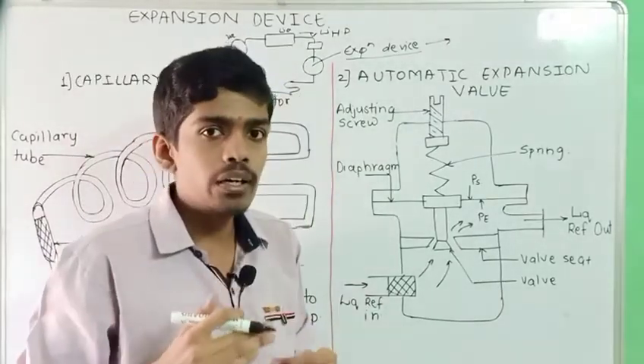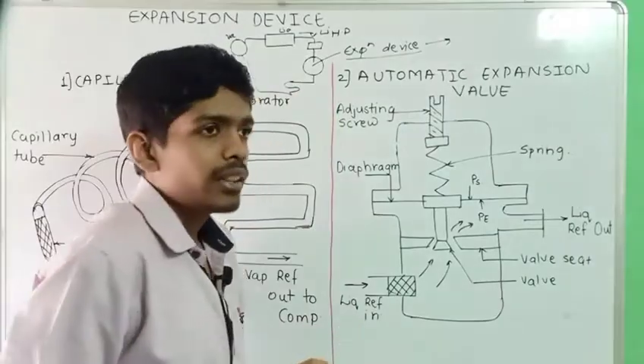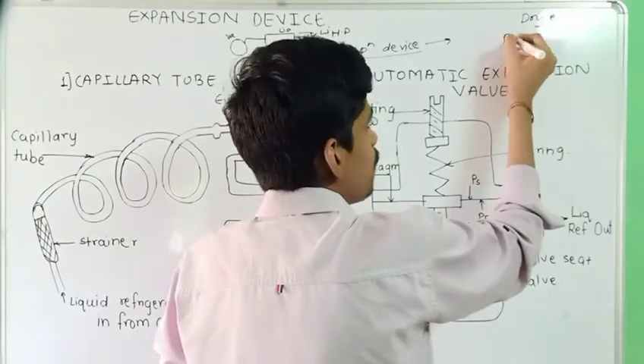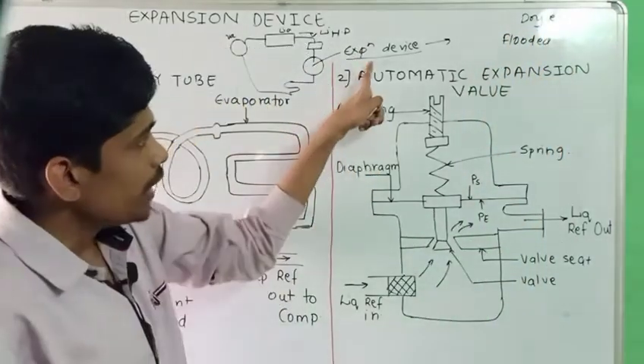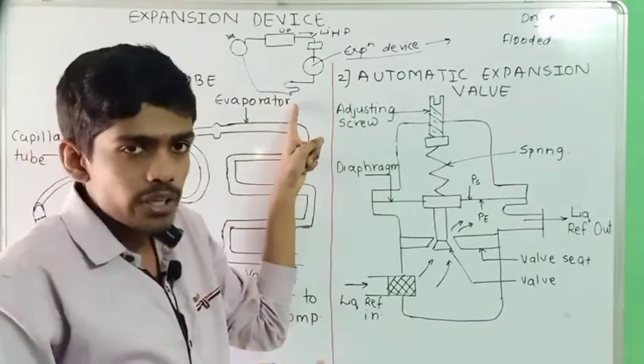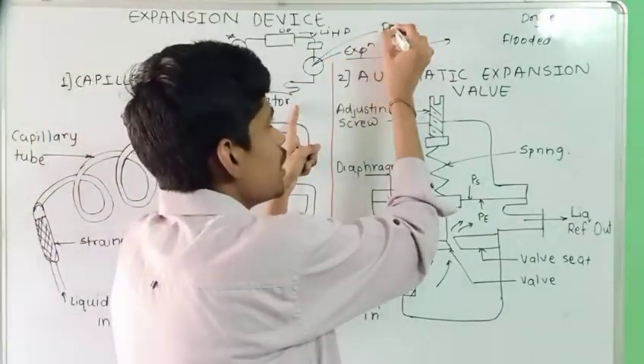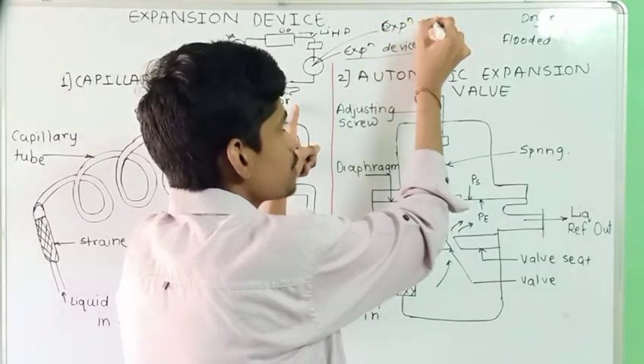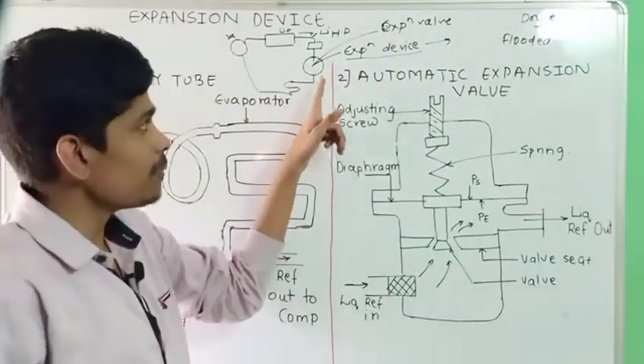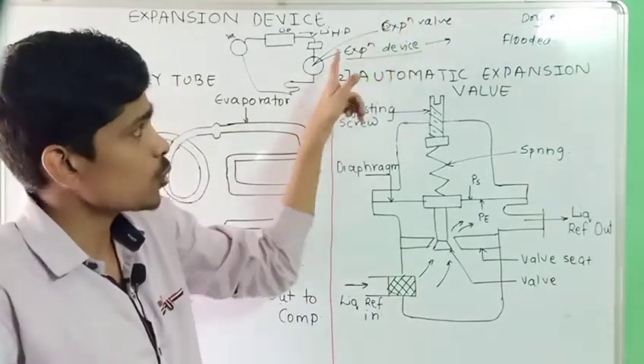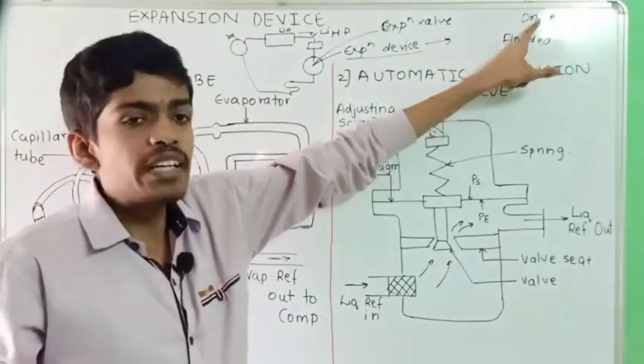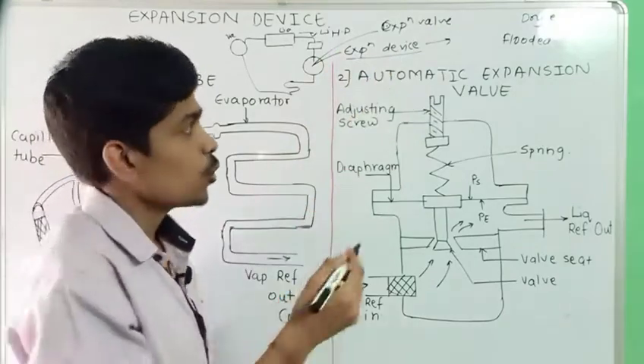There are two types of evaporator: one is the dry expansion evaporator and another is the flooded type evaporator. When a dry expansion evaporator is used, the expansion device is known as an expansion valve. When a flooded type evaporator is used, the expansion device is known as a float valve.